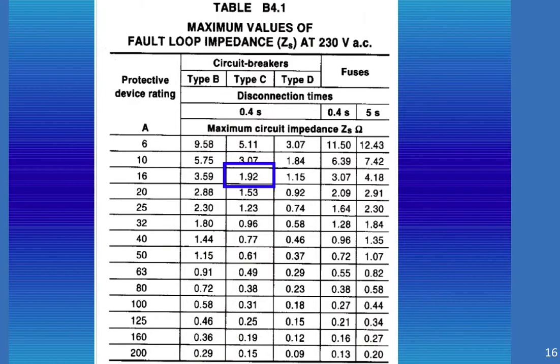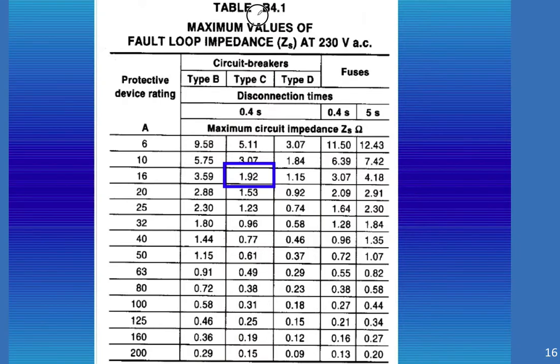So this is table B4.1. We're working with a C-type circuit breaker because they didn't tell us otherwise. We knew it was 16 amps. So this is the column that we're interested in. And it's a C-type where the two cross. This is the value we're interested in. And we know that if our circuit impedance is less than 1.92 ohms, then we're going to disconnect in 0.4 of a second, which is acceptable.